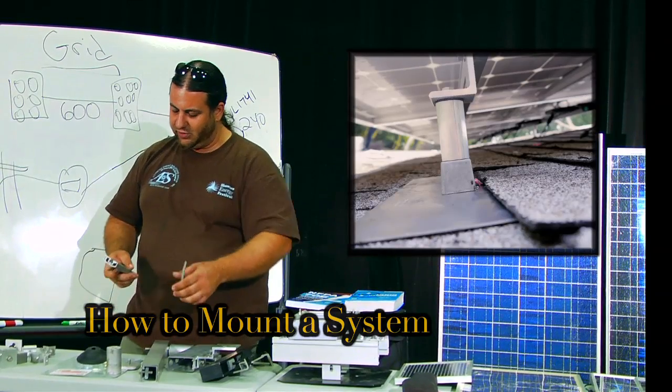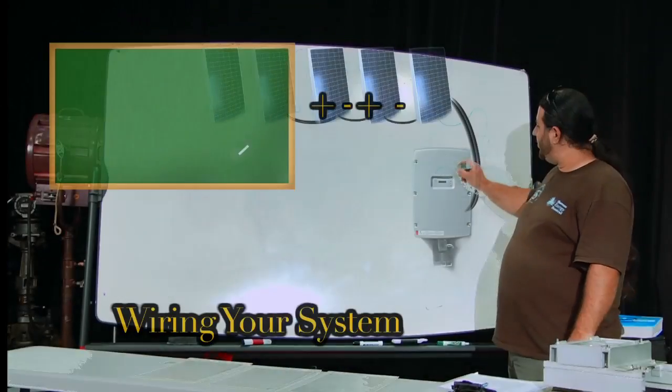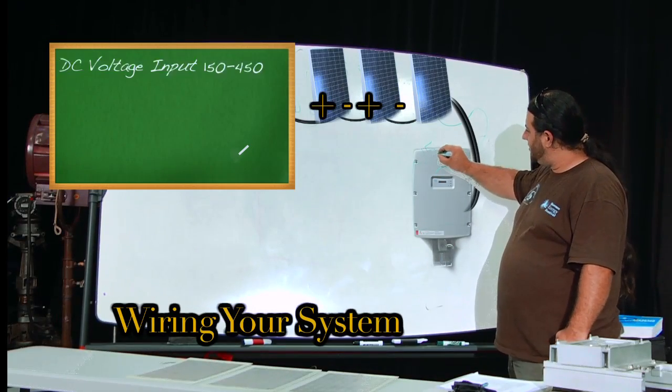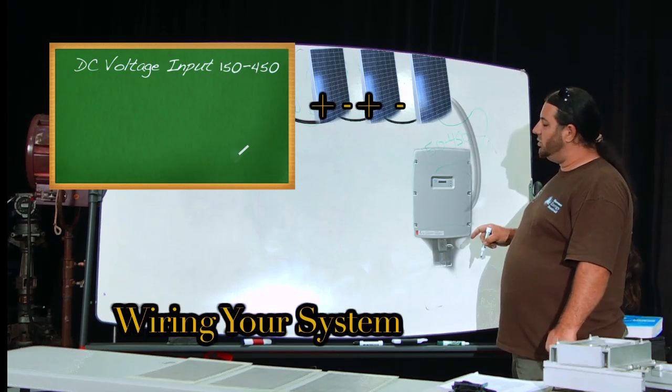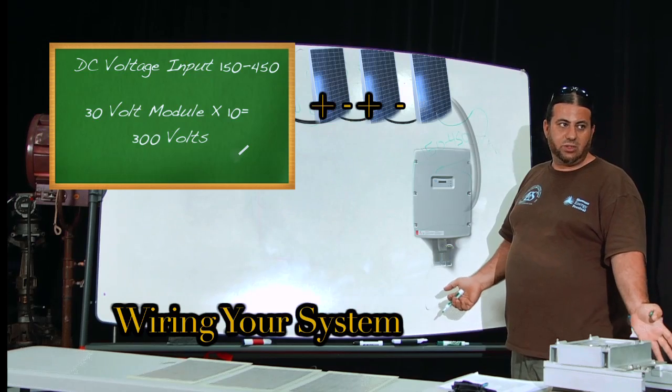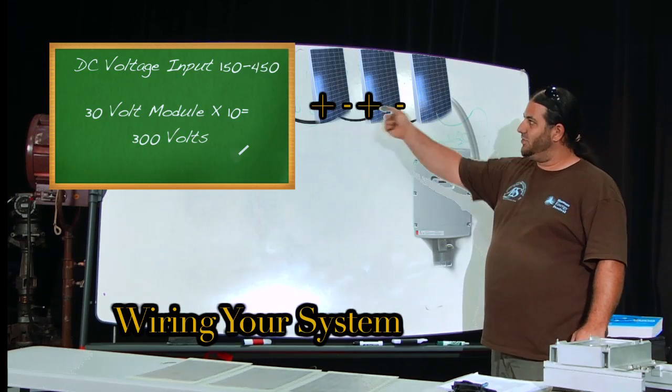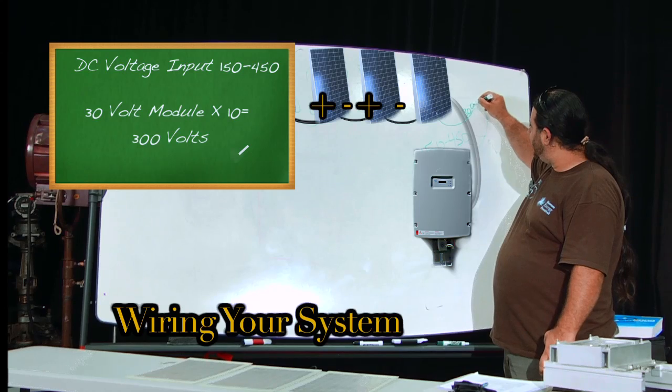DC voltage input of 150 to 450 volts. So if the module itself is a 30 volt module, we could put 10 of them in series and then we would have 300 volts coming in, and that would be within that range, no problem with that inverter.